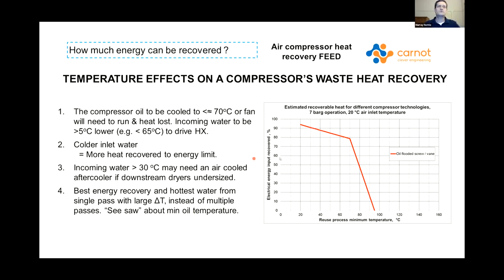The important thing is, the colder the water coming in, the more heat you can recover. If your water coming in is too hot, you won't cool your air down enough, so your dryer and downstream equipment might be undersized, so you need to be aware of that. And for the best energy recovery, you need to go for a single pass of the water. So you need to get as big a temperature rise in that water as you can. And what I mean by that is, to have that 70 degrees there in the water, if you've got say a 5 degree approach temperature in your coolers, the water coming in needs to be at 65 degrees.